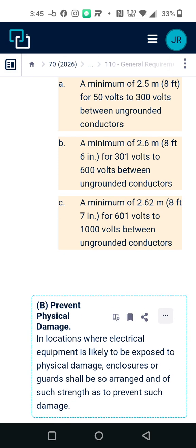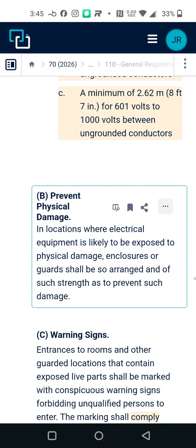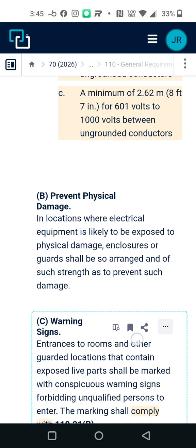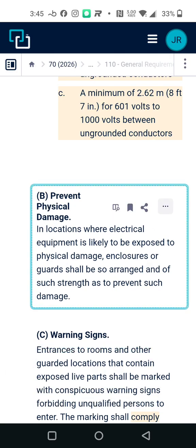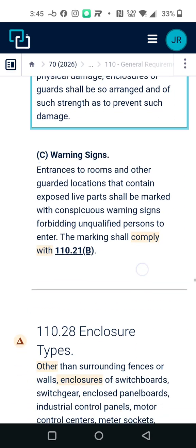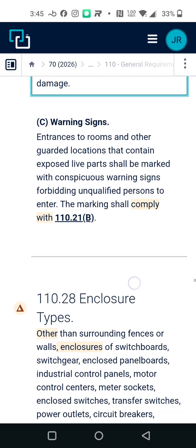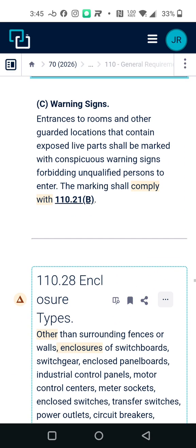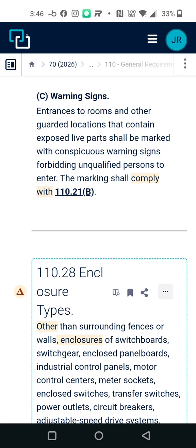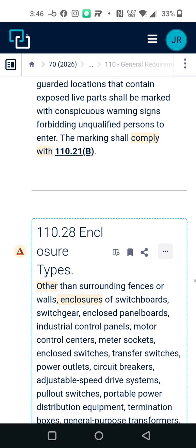Prevent physical damage. In locations where electrical equipment is likely to be exposed to physical damage, enclosures or guards should be so arranged and of such strength as to prevent such damage. Warning signs: entrances to rooms and other guarded locations that contain exposed live parts should be marked with conspicuous warning signs forbidding unqualified persons to enter. The marking should comply with 110.21(B).